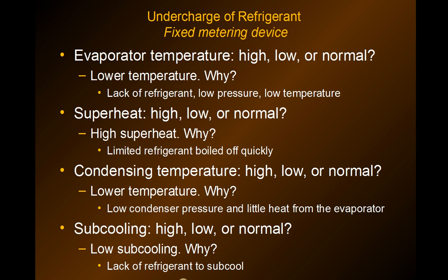The condensing temperatures are going to be lower because of the lower pressure from less refrigerant, and there's not as much heat coming from the evaporator since most heat is absorbed by boiling refrigerant — with less refrigerant, less heat goes out to the condenser. The subcooling will also be lower than normal because there's simply not enough refrigerant in the system to produce any meaningful subcooling.